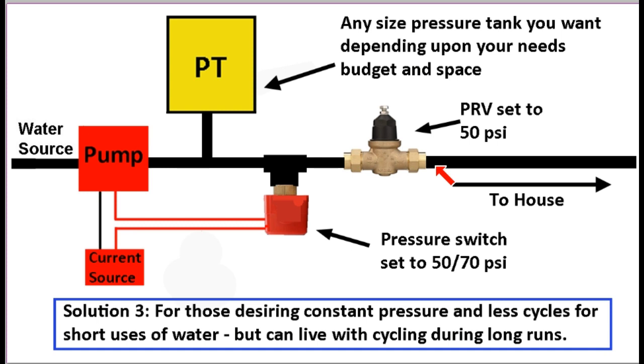Now, there's also an advantage to this, several advantages over a cycle stop valve with this system. When you stop using water, the pressure tank will fill up at a regular rate. It won't be filling up at this dribble rate of 1 gallon per minute. It will fill up quickly. And then the next time you start up your water again, you won't get the fluctuation. So with the cycle stop valve, you get the dip, and then you get the rise, and then you get the stable. But here, since you're starting at 70 psi, but you have a pressure reducing valve reducing it to 50, you'll never get any fluctuation. So whereas a cycle stop valve has a fluctuation at the beginning of a run, every time, before it becomes constant, here you will have a constant pressure the whole time.